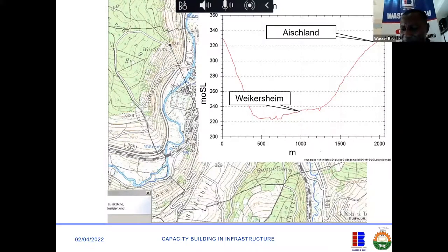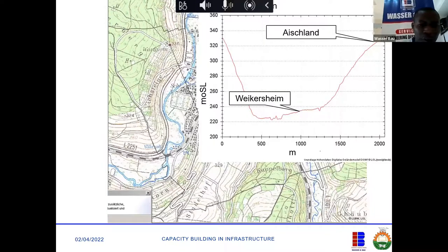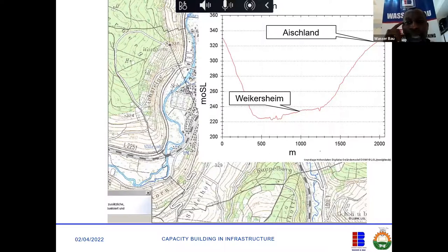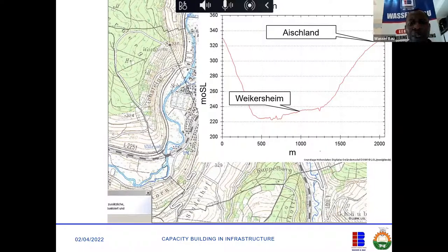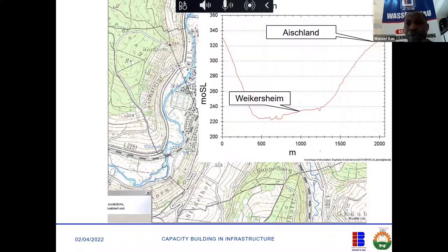There is a condition that pressure must not be more than 8 bars in a water distribution network. The reason being that the components of the system - such as your pipe, pumps, and valves - some of them cannot withstand more than 8 bars. So in your design, if the pressure difference between one point and the other is more than 8 bars, it means you need to break the system - you need to zone the system into zones.